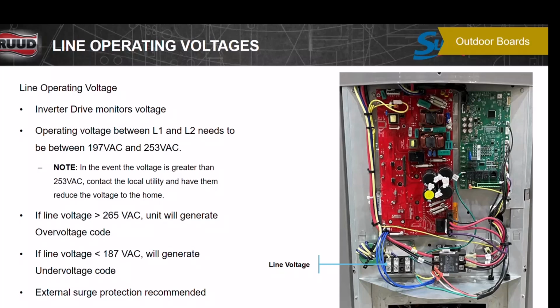Normal compressors won't start if the voltage is close to 187. You know, we have hard start kits, and even those won't start. These units will. If our voltage is down to 195 volts, it's going to work. External surge protection is recommended. That means a surge protector. You can get a surge protector for about $80, under $100.